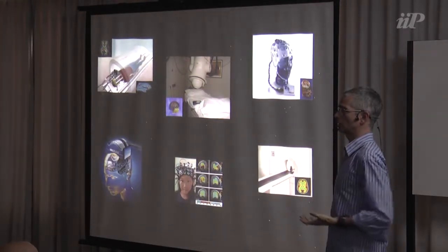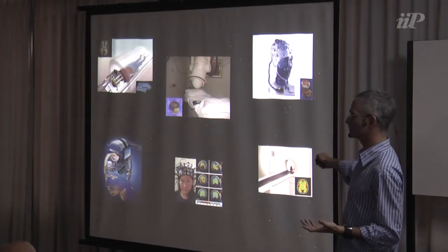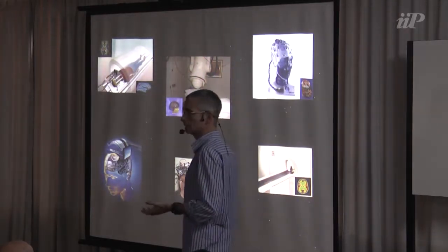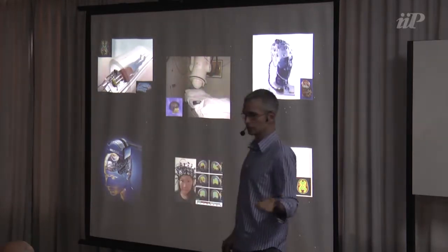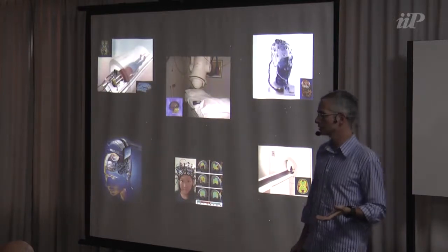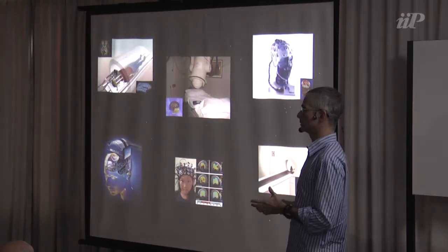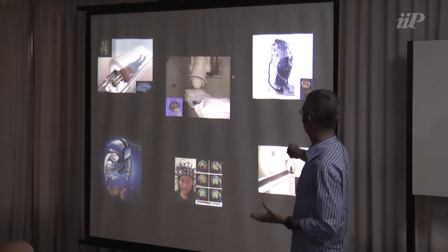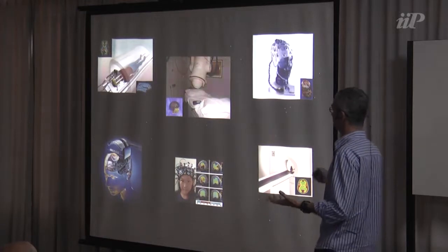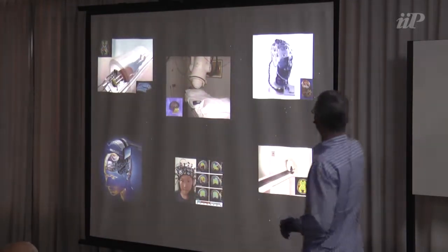And the operational cost of this system is high as well, because some of these systems consume about 20 to 30 liters of helium a week. And we are talking about around $20 for a liter of helium. So you do the math. It's not a cheap system. And what you increase when you compare an MEG with EEG is the spatial resolution, which is much greater than the EEG.